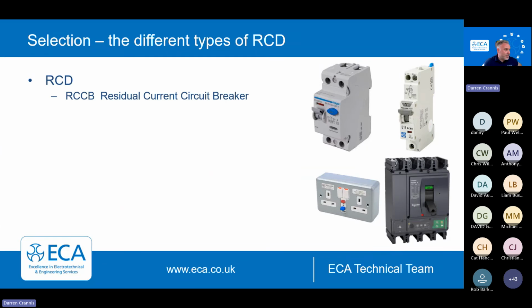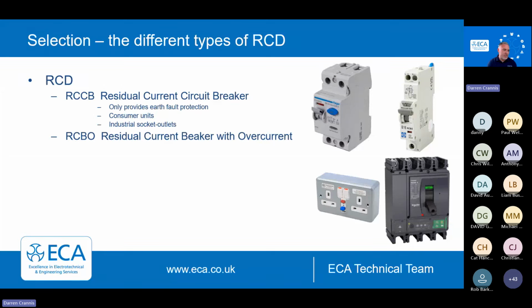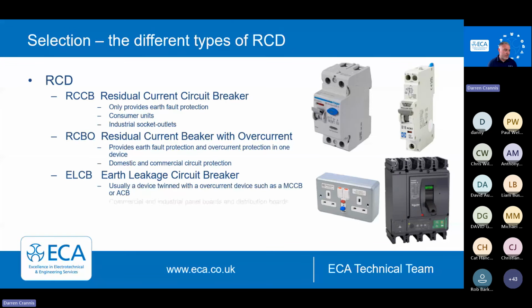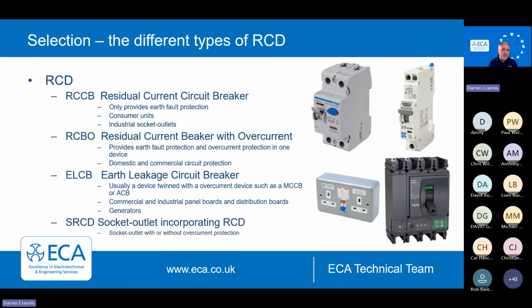How many different types of RCD have we got? Well, RCD, or residual current device, is just a generic term which encompasses quite a few devices. So we've got the RCCB. You may see these a lot in split load boards, typically built to BS EN 61008. You might get some of the older variants to BS 4293, and they're residual current circuit breakers without overload protection.